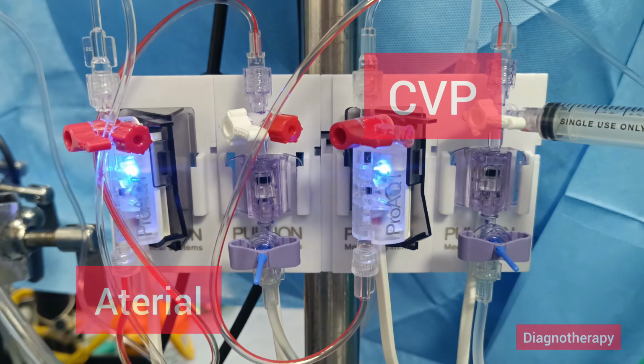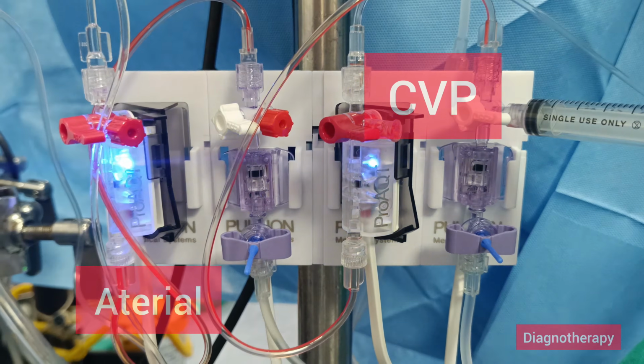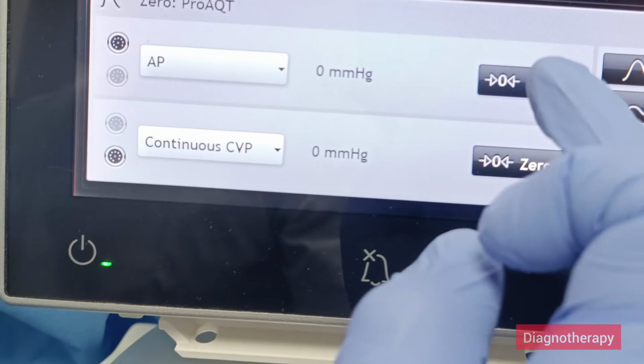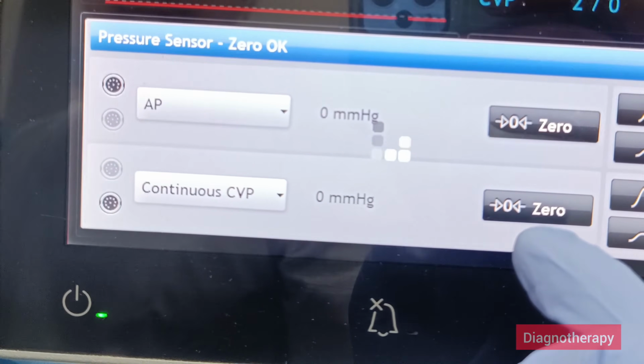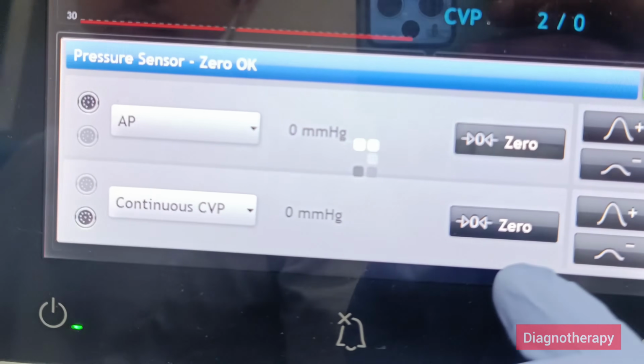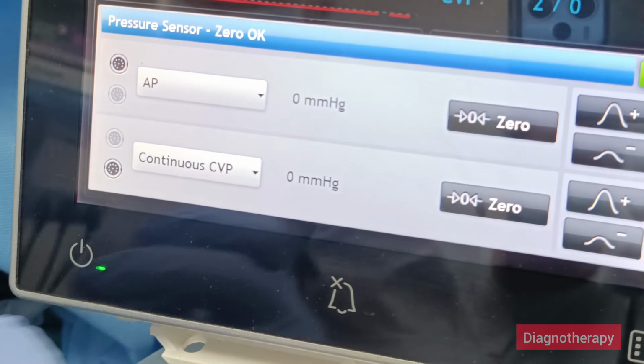After attaching, we need to do the zero calibration. For zero calibration, we need to go to the monitor, press 0. First, we'll be doing the arterial pressure. Arterial pressure will be 0. After the timer has gone, it is 0.